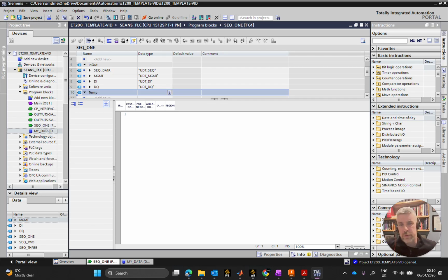We don't have an input to say that the light has come on. There is no photoelectric sensor that we're using to say yes, that coil has illuminated. So where we need to turn on a light, the validation for that light being turned on is checking the output to validate that yes, it actually has been turned on. That's where the DQ comes in.